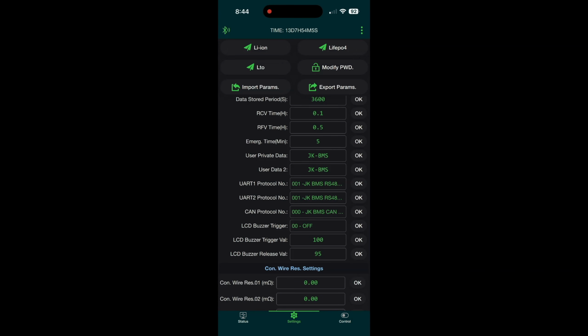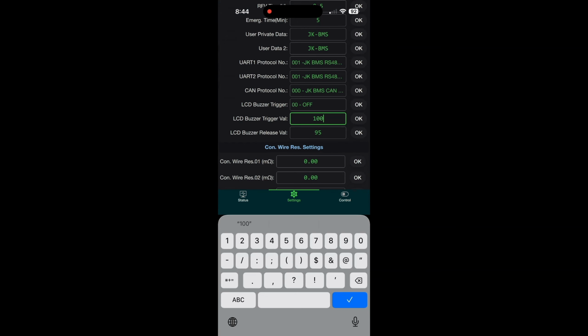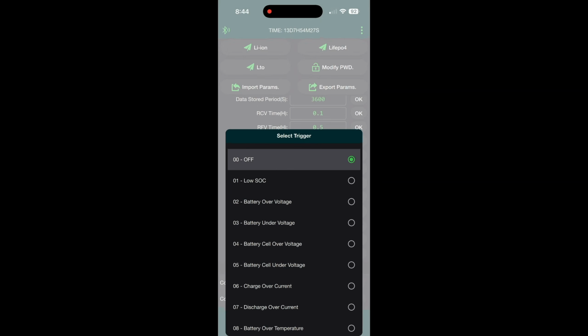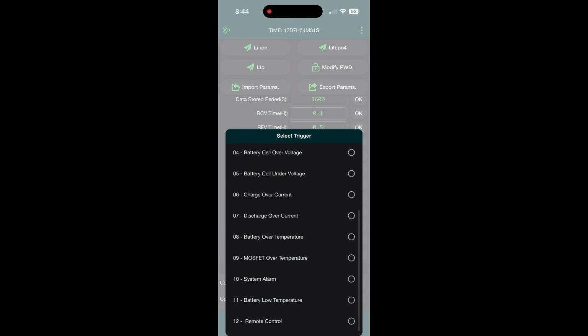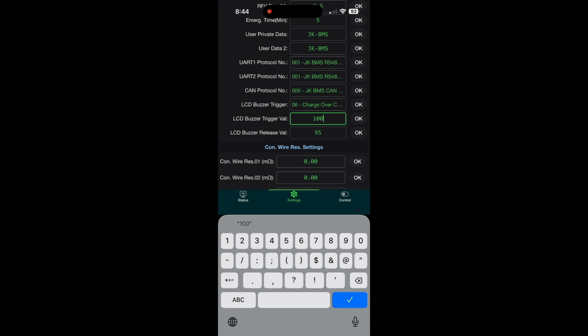The LCD buzzer trigger value - this relates to when the alarm will trigger. If you've got it set to 100, it means that when 100% of the LCD buzzer trigger is met, it will sound the alarm. So if you've got a system alarm set, it basically goes off as soon as that's triggered. However, if you've got a charge over current setting, it means that as soon as it reaches that alarm level, it'll go off.